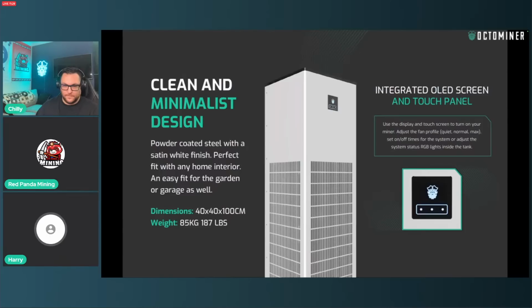Some of the main things you can use the OLED for, or do on the control panel of the unit, is switch between fan profiles. Usually on the standard setting, it's set to auto, meaning it will keep the immersion liquid temperature in the optimal range and adjust the fan speed and pump speed accordingly. But you can also set something like quiet mode and turn those settings down to manually optimize it more, or go full manual and set everything to 100% if that's what you want to do.